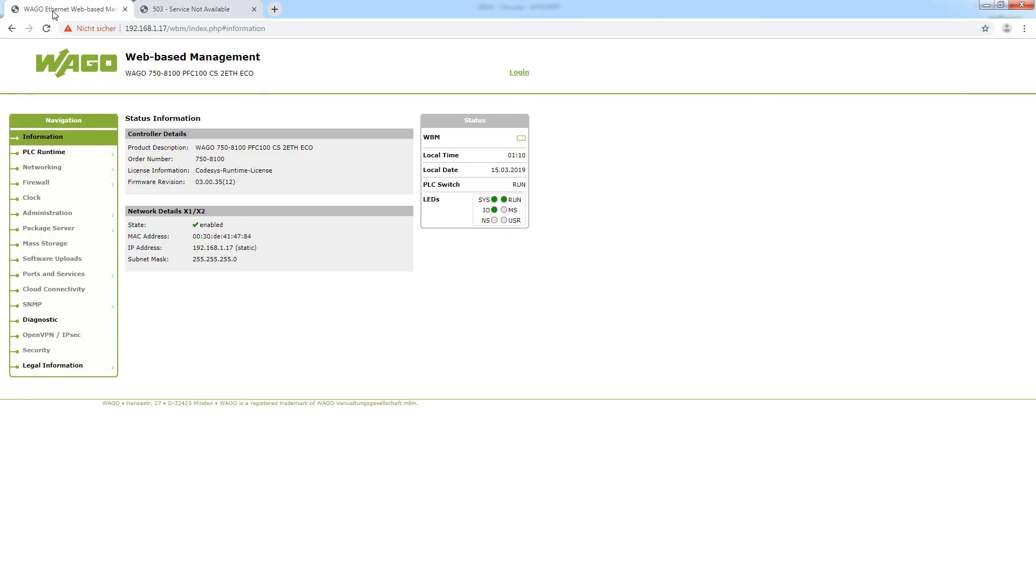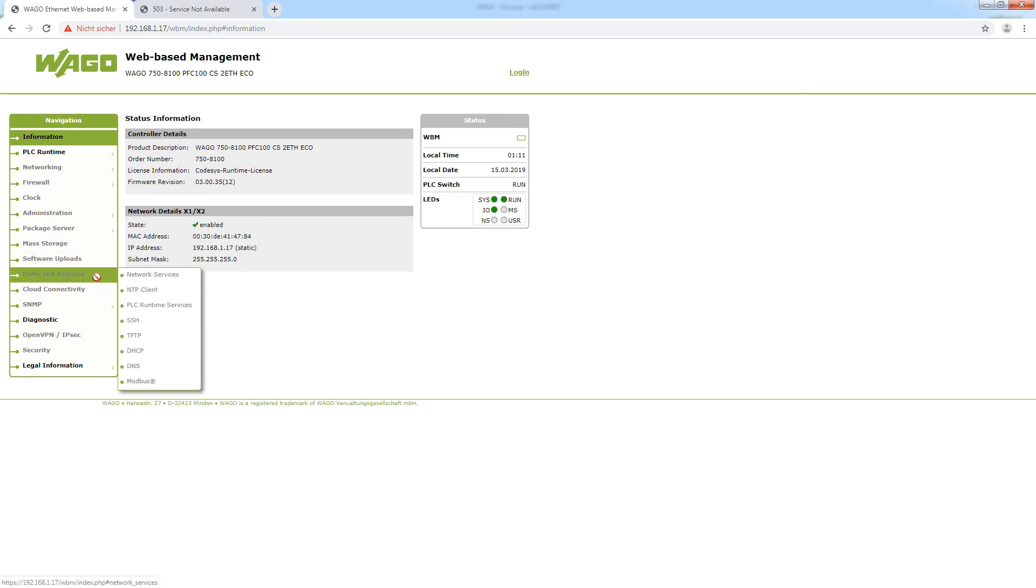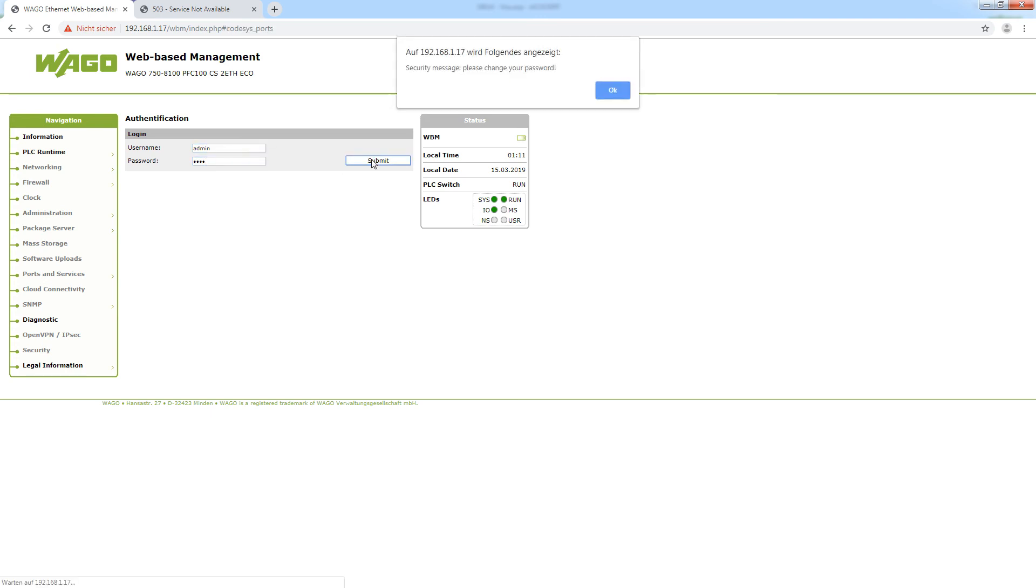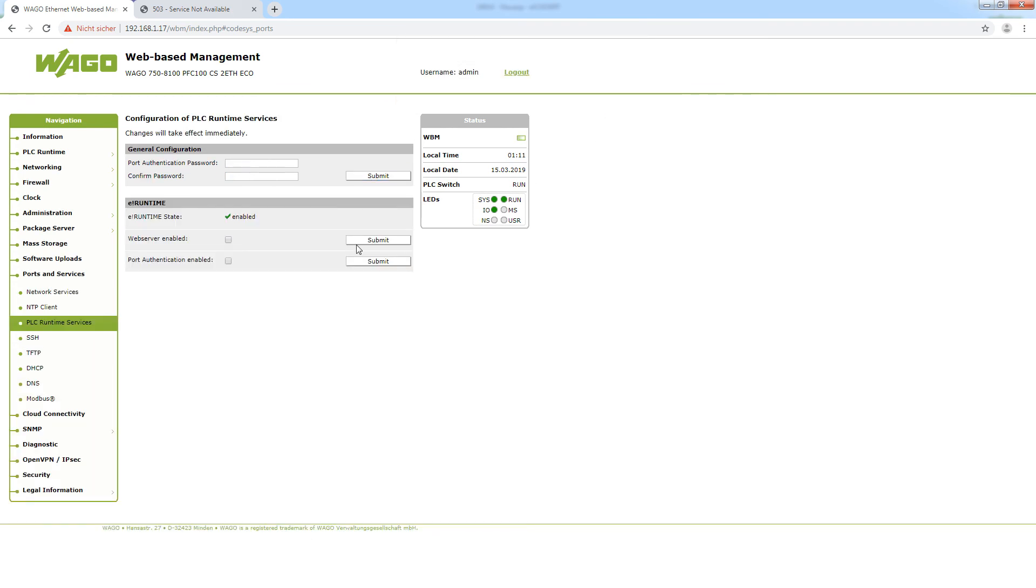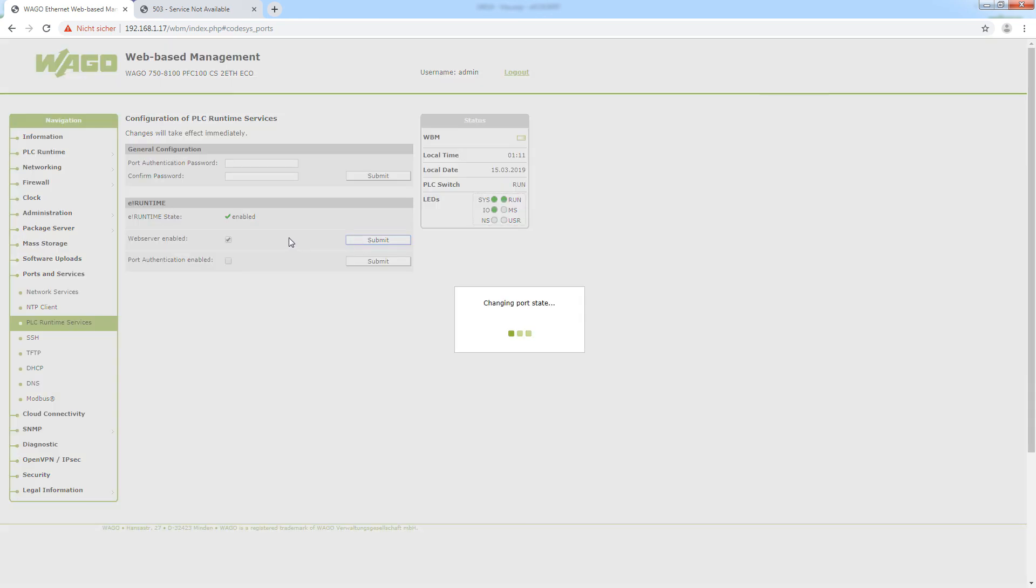To activate it we just go to the web-based management by typing in the IP address slash WBM. And then we go to ports and services PLC runtime services. Here we quickly log in. Standard password is WAGO. And then we can check if the web server is enabled. Here we can see it is not, so I will select web server enabled and submit it.